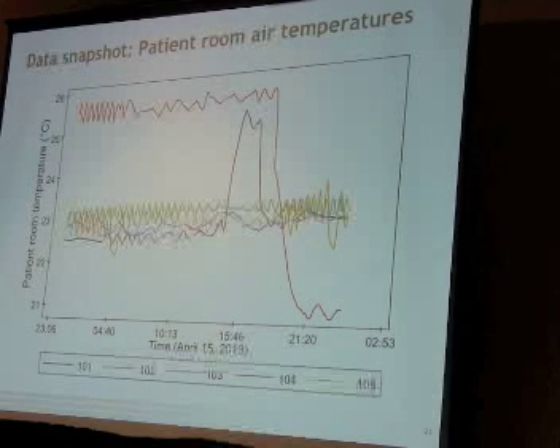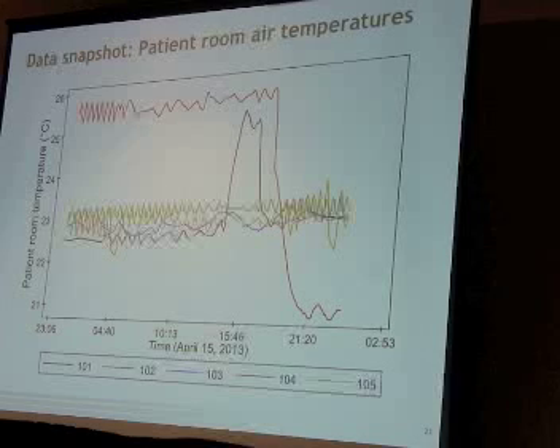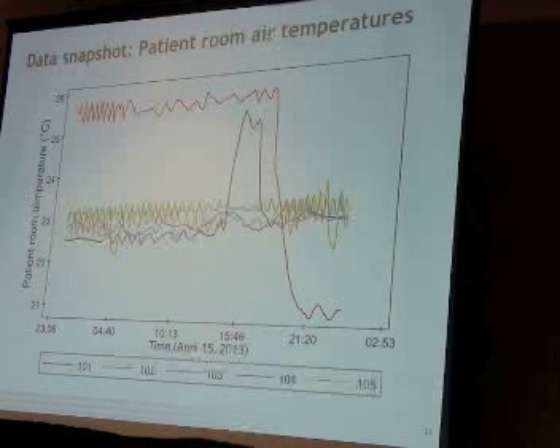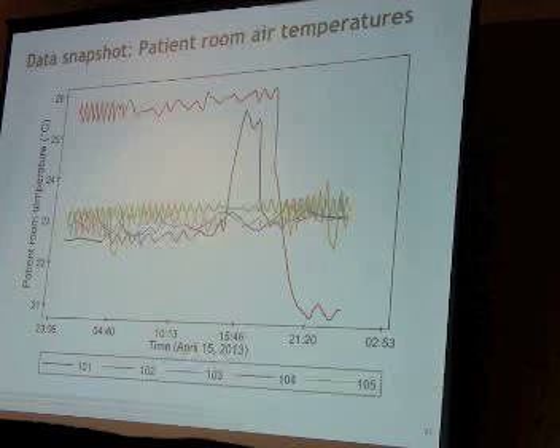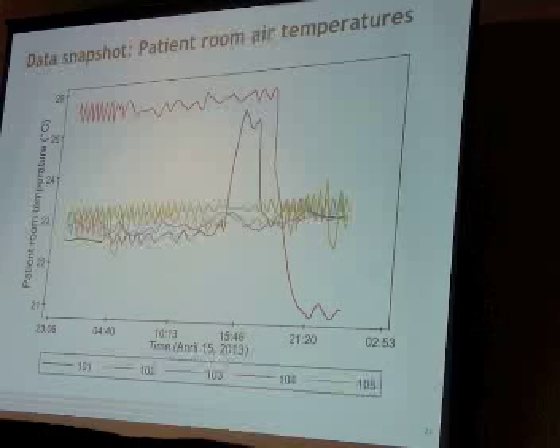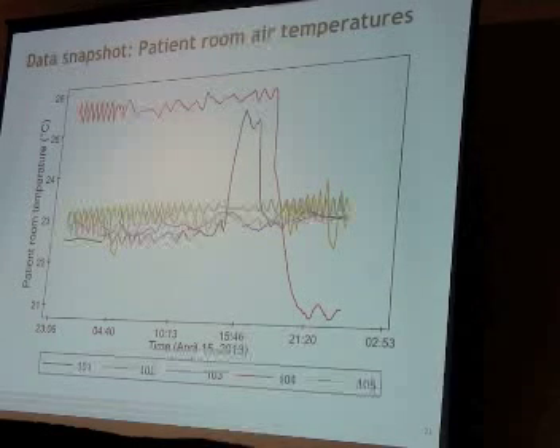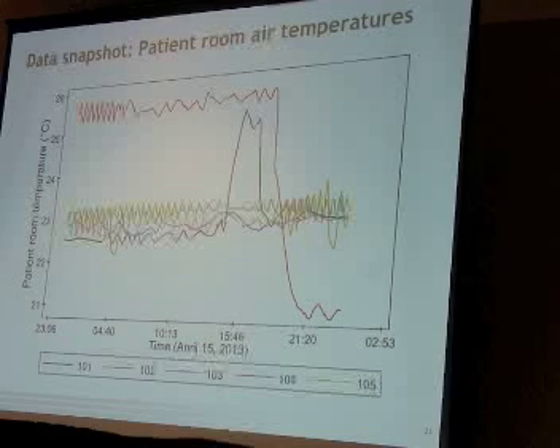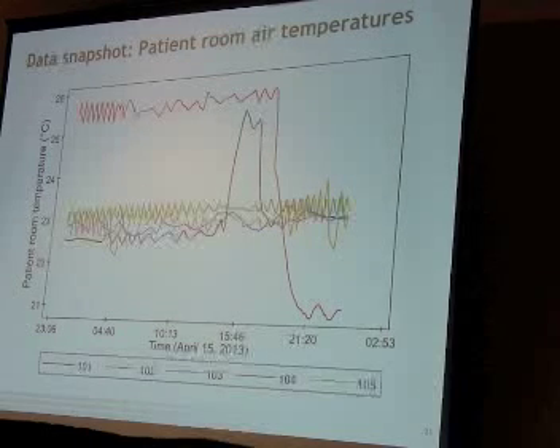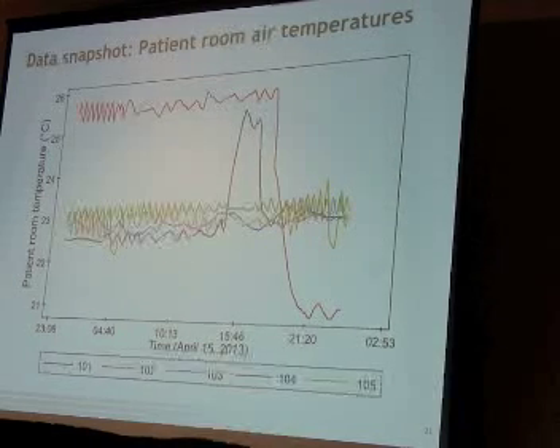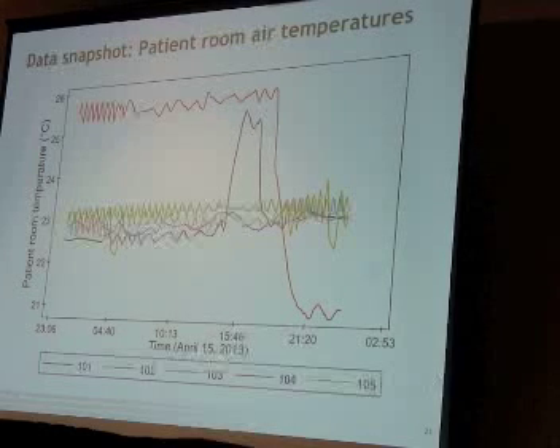So here we have patient room temperature from those little data loggers on the wall for 5 different rooms on the 9th floor. We have code names for these rooms - 101 through 105, shown in black, green, blue, red, and orange. This is just a 24-hour period pulled out of our data set. We see oscillation, that's temperature controlled by the HVAC system, and you also see some dips, right?